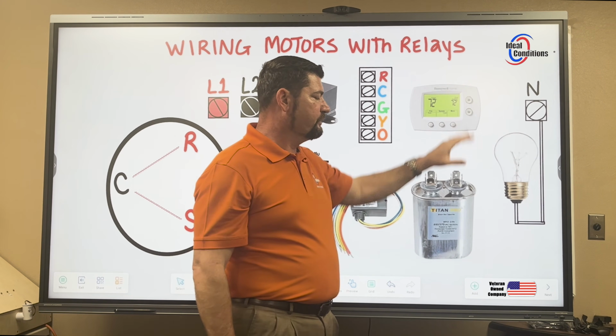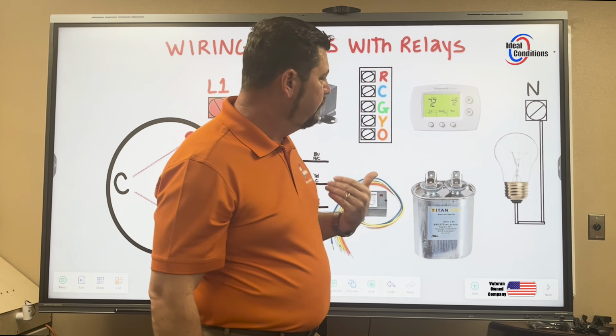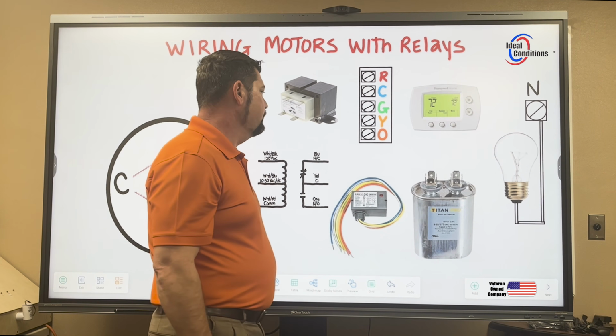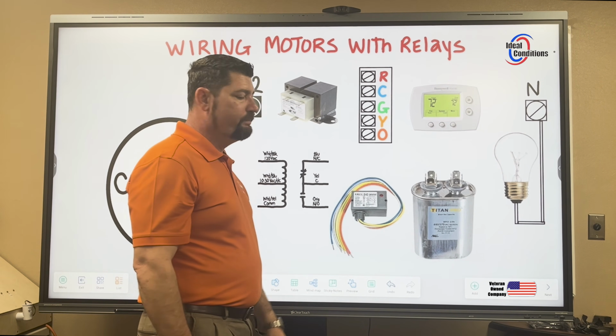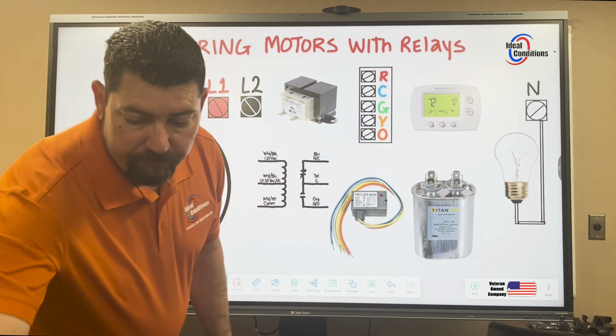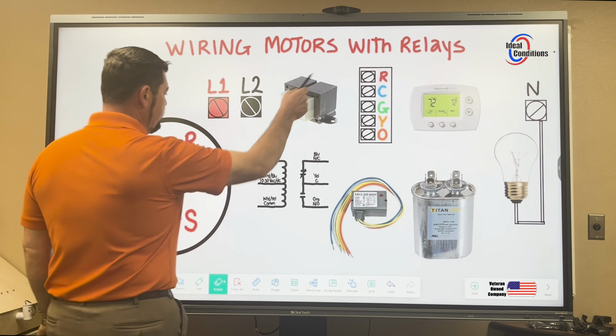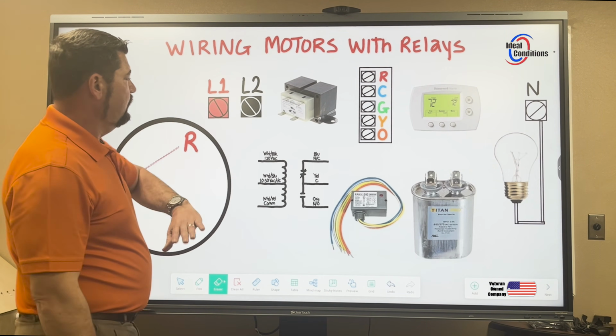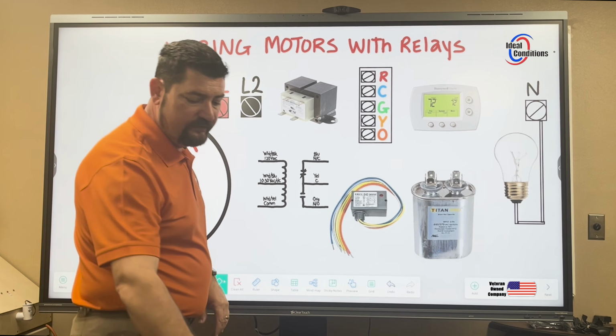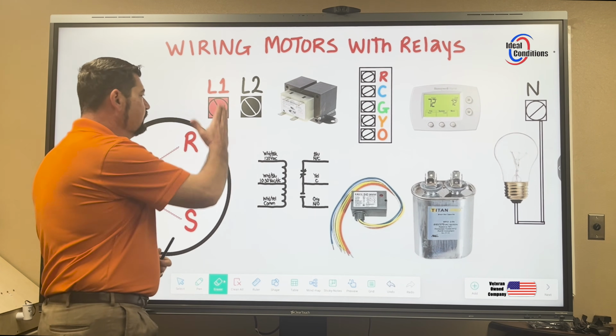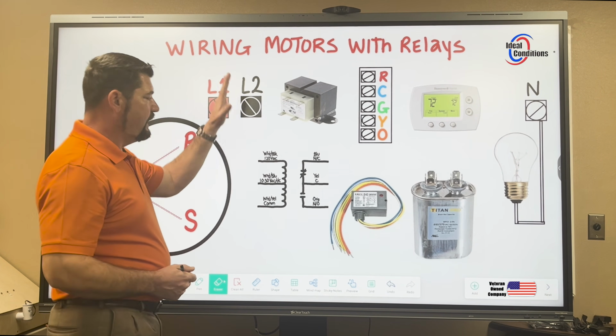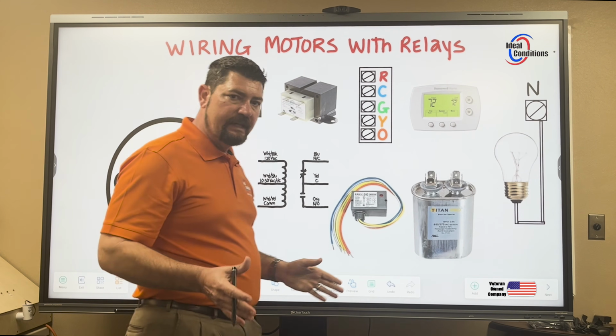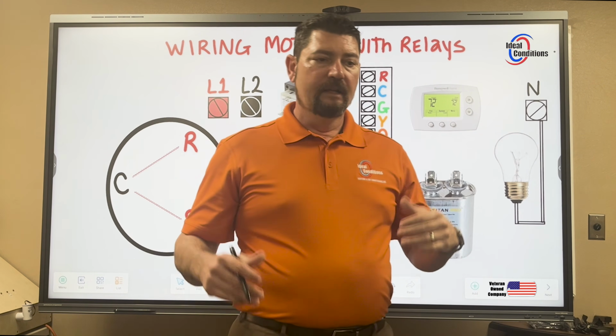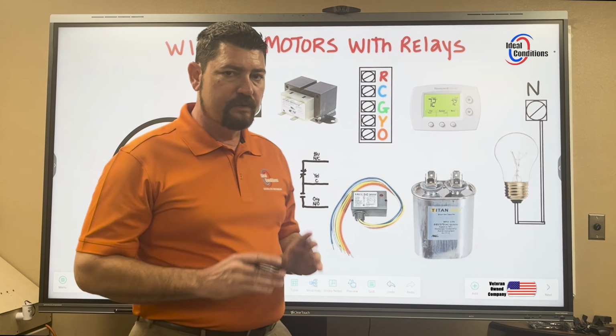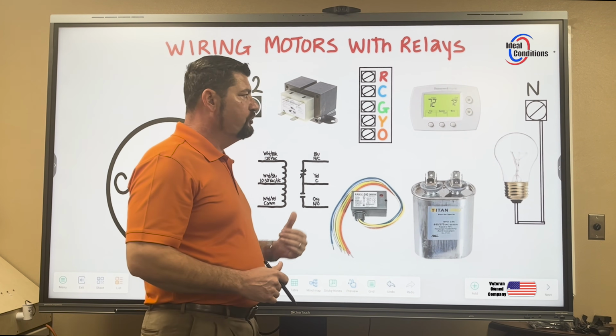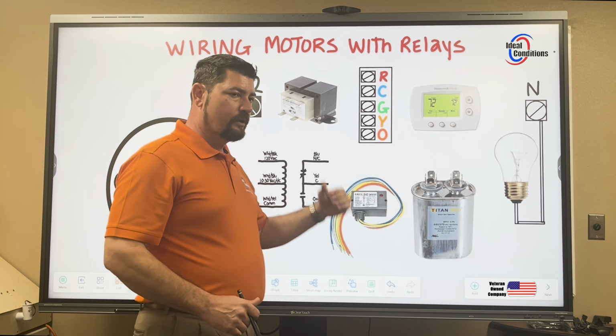So we've introduced some of these other components here, not for the video's purpose, but because it is within your scope, and we want to make this as simple as possible. We have L1, L2, and we have 24 volts. Let's go ahead and practice safety. How we do that is we're going to do one leg of power at a time. Once we're done with that, we're going to inspect that leg of power. If everything looks good, we're going to go to our next leg of power and wire that up. Once that leg of power has been inspected and we're confident with that, then we're going to go to our secondary control voltage and wire that up.